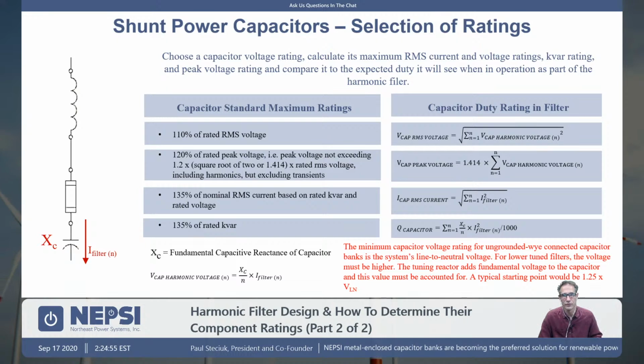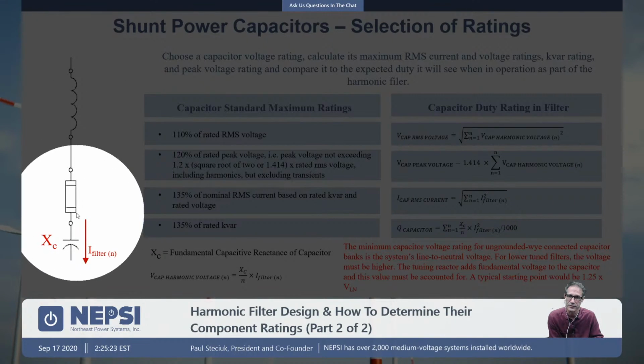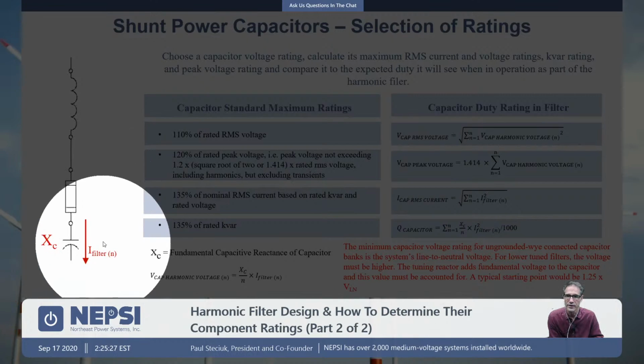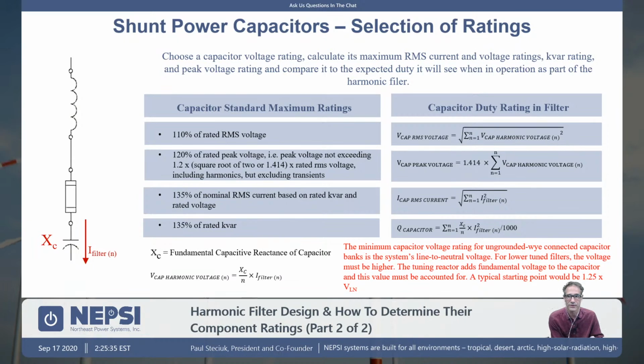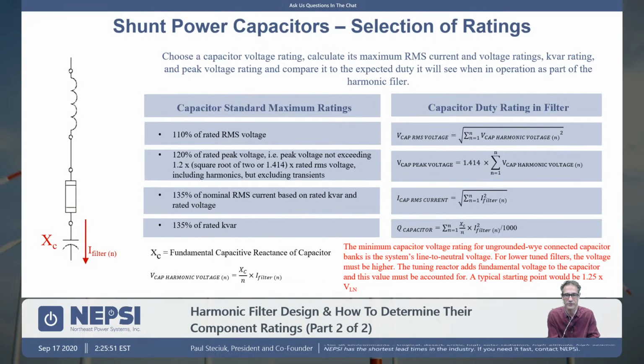We're going to pick a filter capacitor based upon these four ratings here: its RMS voltage, its peak voltage, its nominal RMS current rating, and its rated kVAR rating. Remember, the harmonic analysis program has calculated the harmonic filter current, I filter here. It's calculated the current flow through the capacitor. With that current flow through the capacitor, we are able to calculate these values here. So we're able to calculate the voltage. It's just the filter current at each frequency times the capacitive reactance at that frequency. Remember, the capacitive reactance will drop off by the harmonic number. So the third harmonic will have one third the value of X_C at the fundamental.